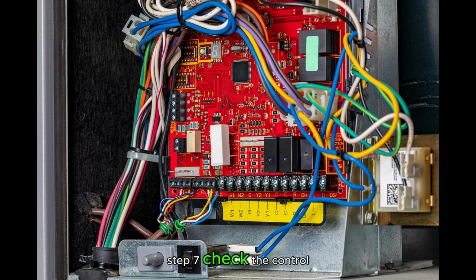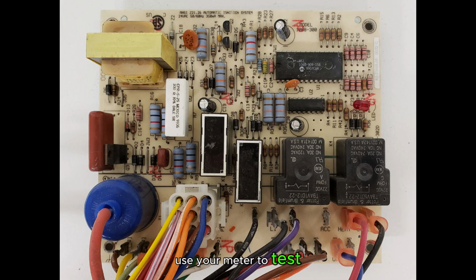Step 7. Check the control board. If everything else checks out and still nothing runs, the board might be the problem. Use your meter to test signals coming out of the board. R, G, Y, W, O. Boards can fail quietly with no visible burn marks. Be sure you've checked everything before replacing it.